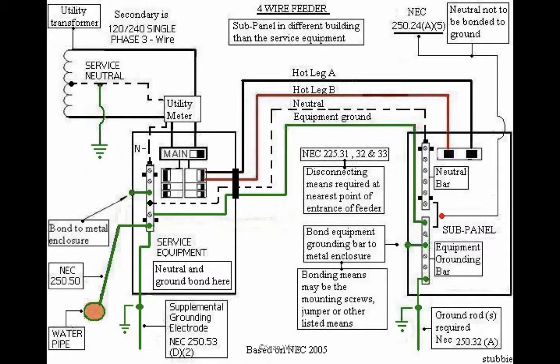It wasn't too many videos ago that we looked at this image, but it's a good image I like for showing you a single point of system grounding. So here's the single point of system grounding. Hopefully you didn't get electrocuted in your house going in there. Make sure you wear gloves. And that's where all the electrodes are connected and all the equipment grounding conductors. So this is right there. That is going to an electrode. That's a water pipe electrode. That is called a grounding electrode conductor, a GEC.